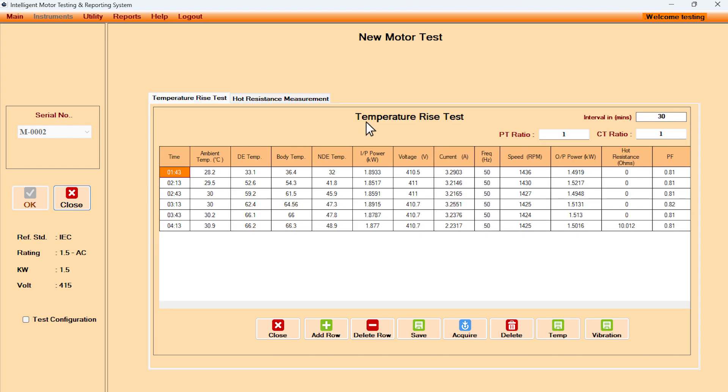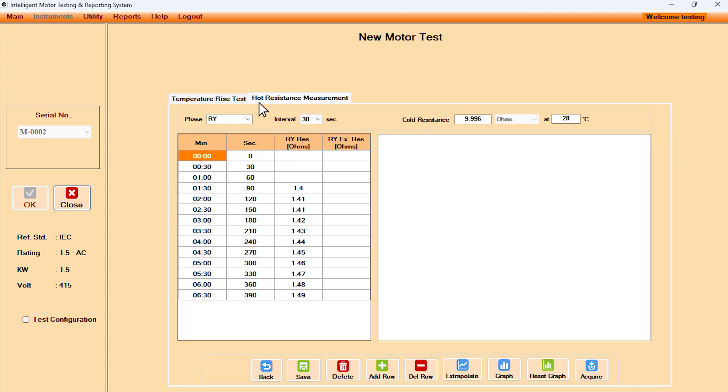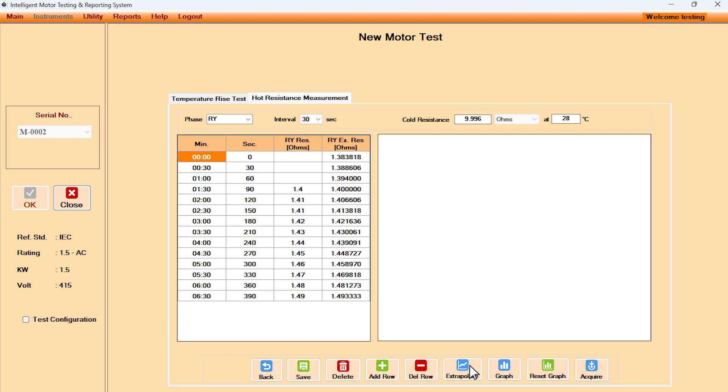In temperature rise test, user sets the time interval for recording temperature and other parameters. As soon as the temperature stabilizes, software prompts user to shut down. During the temperature rise test, the vibrations are also recorded automatically. The hot resistance measurement of the stator winding happens automatically at the set time interval.